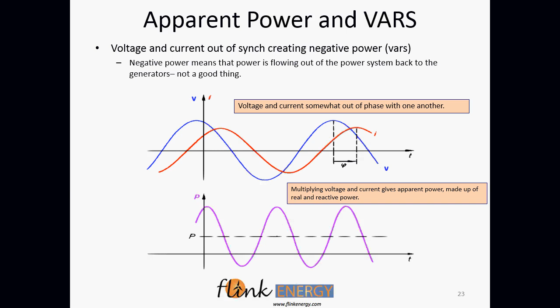And I imagine the equipment that is used to take out, to do power factor correction, and shield the generation plants from all the end uses out there, might burn some energy to do that job? Not much, no. Basically, to fix this problem, you add a little bit of storage to store some current and get it back into place where it belongs. So the current comes in, it stores it up in this device, and then it lets it back out as the current falls. Those are very efficient devices, and they don't store a lot of energy - it's still only for a piece of a second.